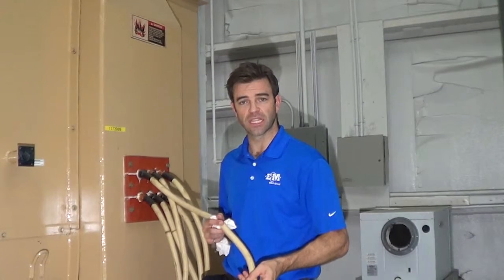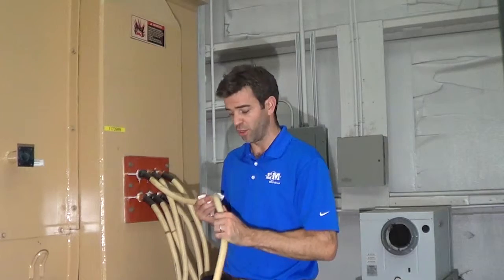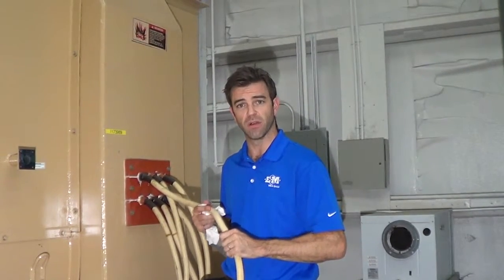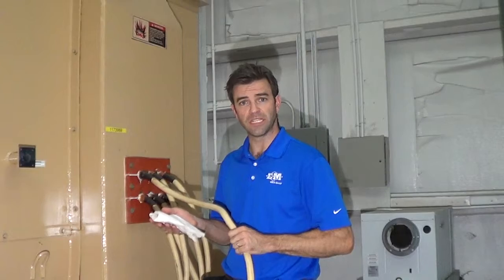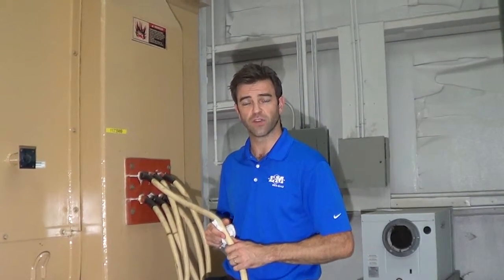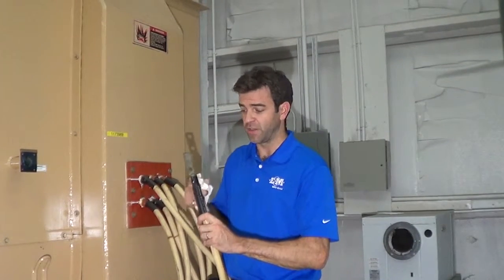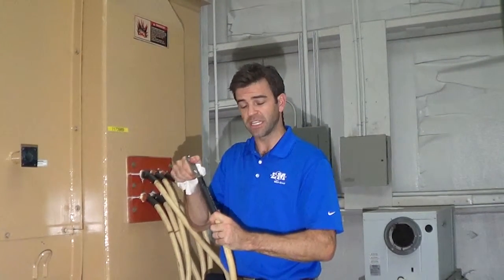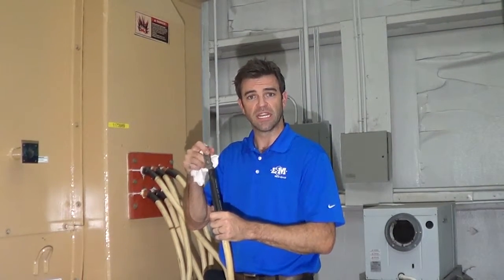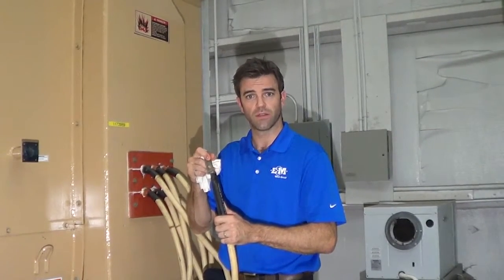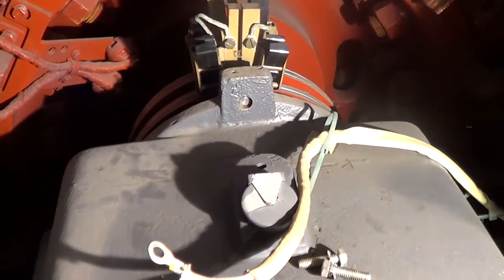Once we've finished electrical testing, let's spend a minute addressing the lead cables. Carefully inspect the lead cable for cracks, splits, or brittle parts, and check the flexibility of each cable. Take a lint-free rag, dip it in denatured alcohol, and clean the cable, as this is a common cause of low resistance for the unit. Check the lug at the end of the cable and ensure that it's stiffly attached and properly protected. A high resistive imbalance in a machine is endemic of a poorly installed lug, so this is something to inspect for as well. Now it's time to perform collector ring maintenance.